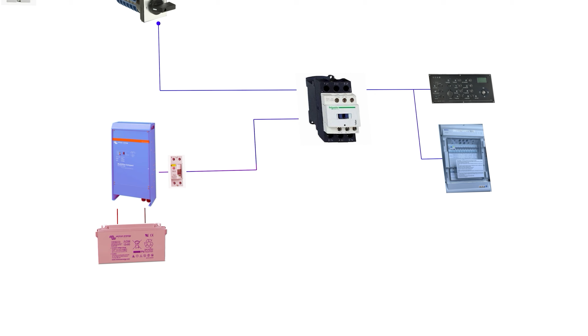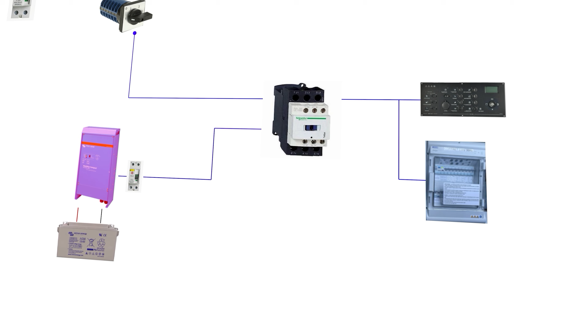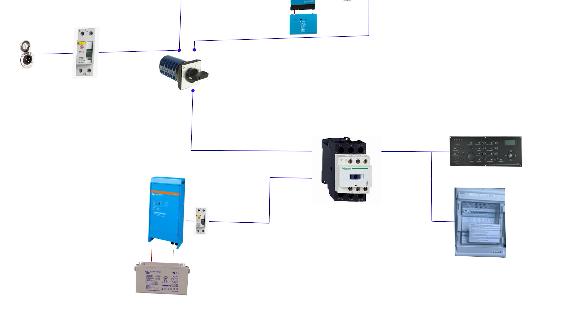Normally closed contacts are on the 10K system, and normally open contacts are on the 3K inverter system. The 3K inverter has its own remote battery switch, or remote on switch, and when actuated, it transfers the load of the boat to that inverter, keeping separation of services at all times.